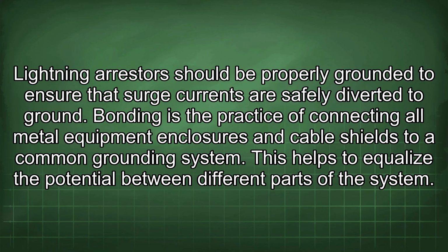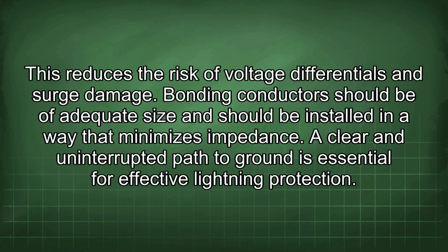Bonding is the practice of connecting all metal equipment enclosures and cable shields to a common grounding system. This helps to equalize the potential between different parts of the system. This reduces the risk of voltage differentials and surge damage. Bonding conductors should be of adequate size and should be installed in a way that minimizes impedance.